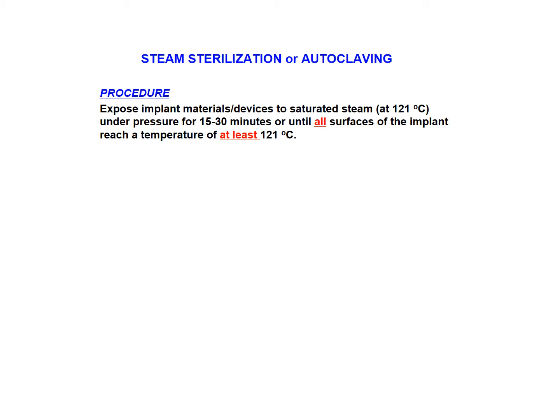Steam sterilization or autoclaving is a widely used method. The procedure exposes implant materials and devices to saturated steam at 121 degrees centigrade under pressure for about 15 to 30 minutes, or until all surfaces of the implant reach a temperature of at least 121 degrees centigrade. Please keep in mind that water boils at 100 degrees centigrade. Therefore, the materials and devices are exposed to temperatures which are above that of boiling water.